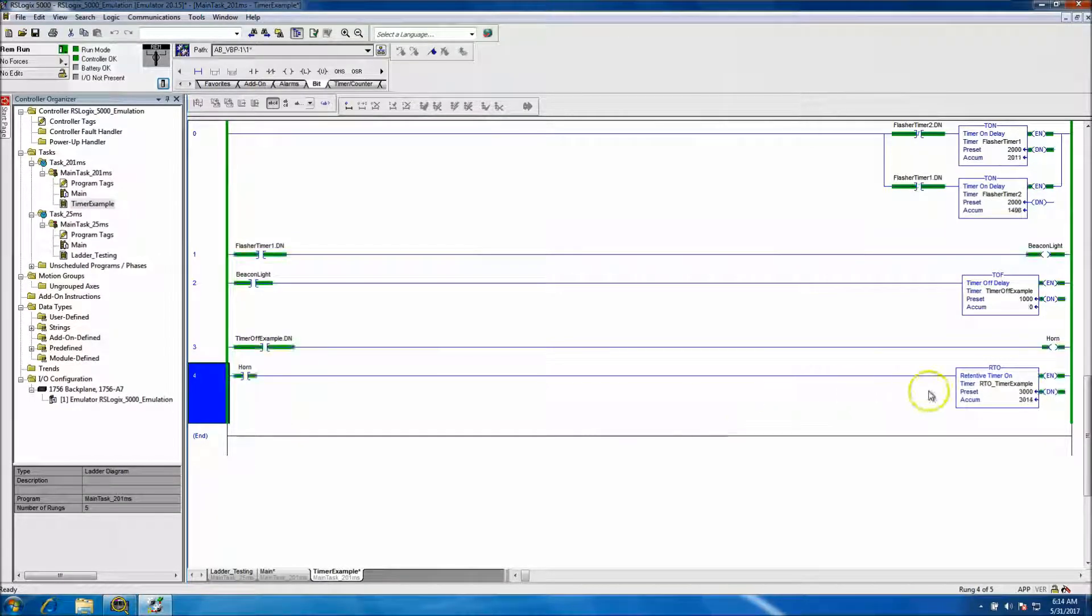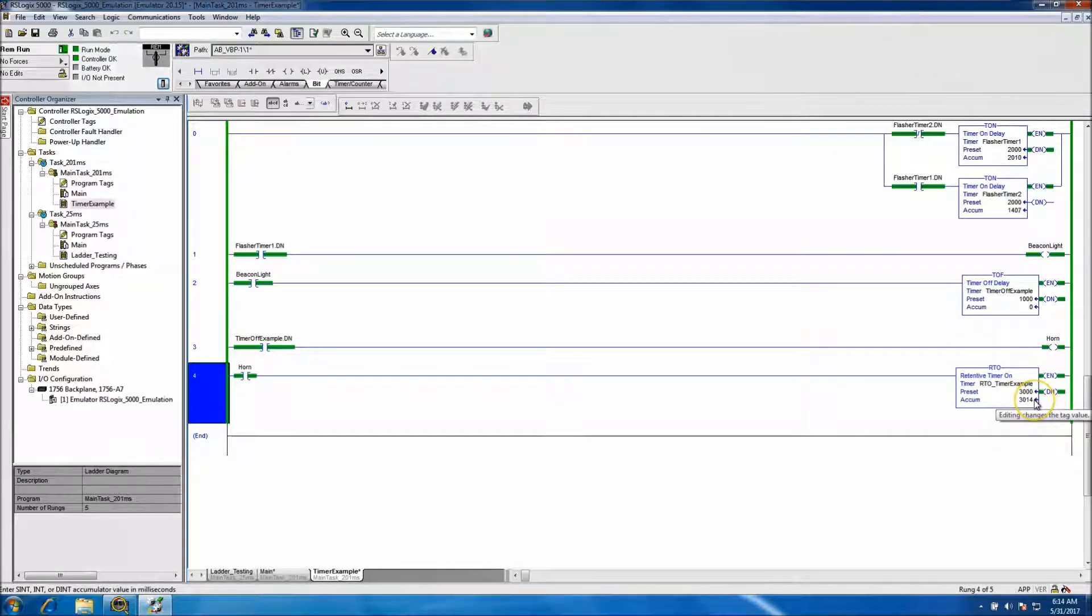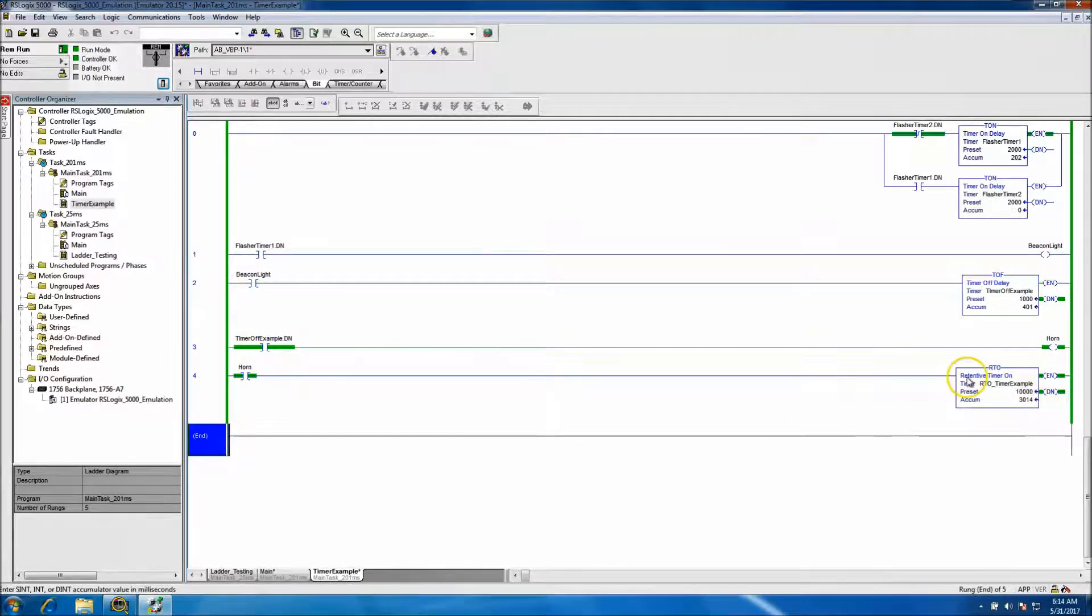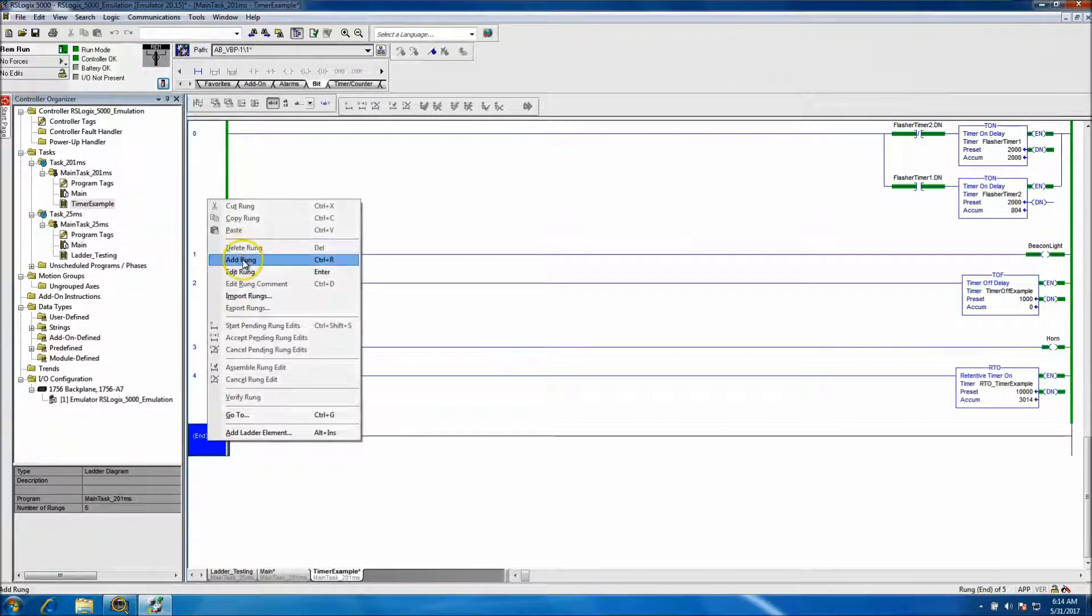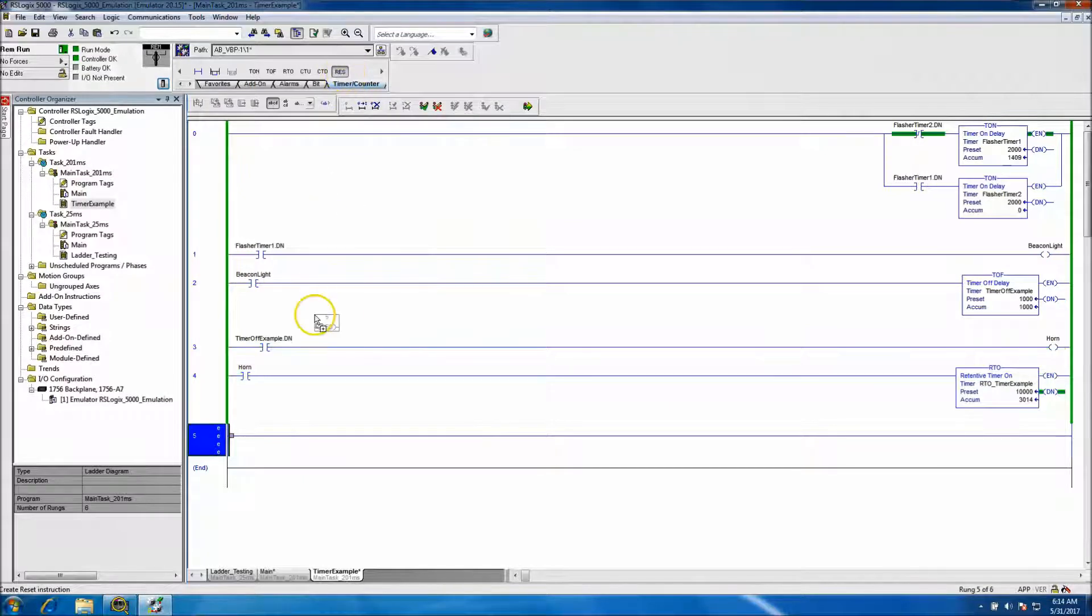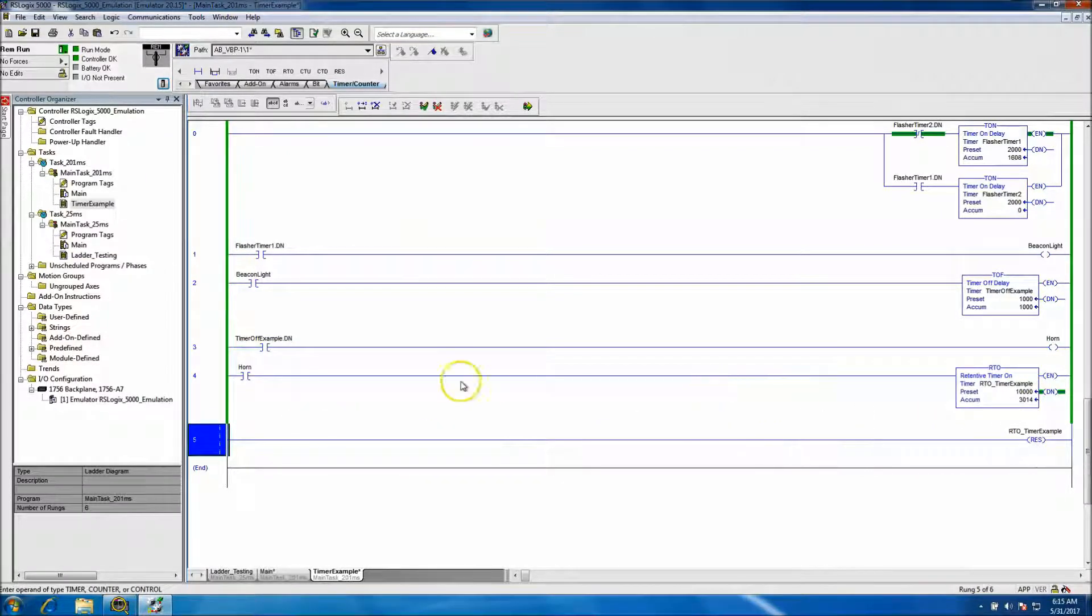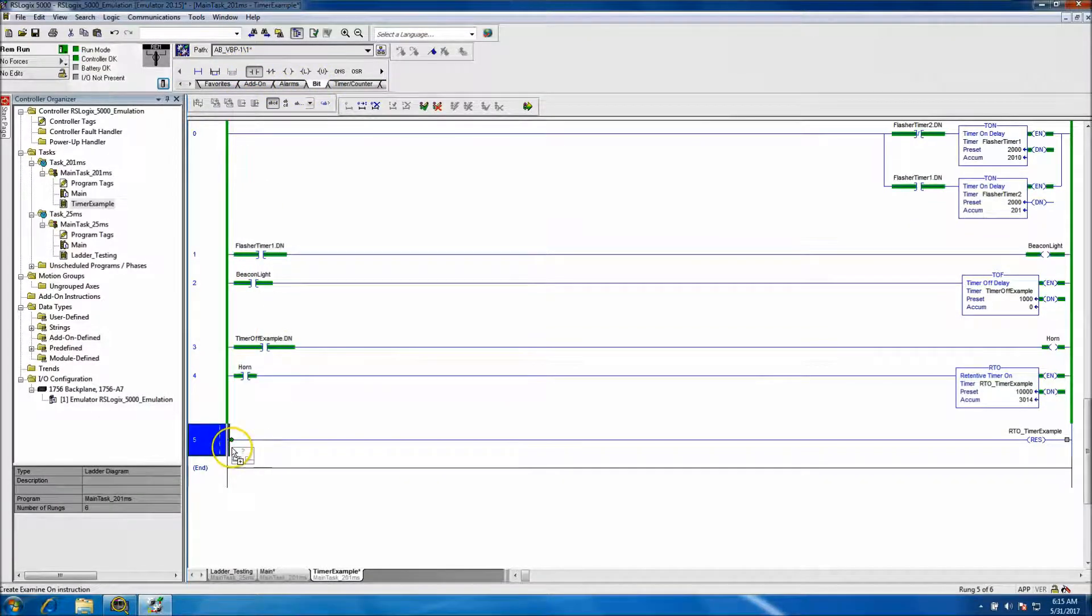The retentive timer basically only times while it's active and then it drops out. Say for instance we put this at a higher number - we also want to put a reset in there. For a retentive timer you actually need to be able to reset it. Just put the whole tag for the retentive timer in that reset command, and then basically once it's done we want to reset it. Just something simple to get an illustration of how this works.